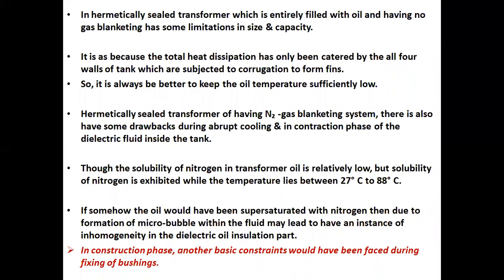A hermetically sealed transformer, which is entirely filled with oil and has no gas blanketing, has some limitations in size and capacity. This is because the total heat dissipation is catered for only by the four walls of the tank, which are corrugated to form fins. So it is always better to keep the oil temperature sufficiently low.